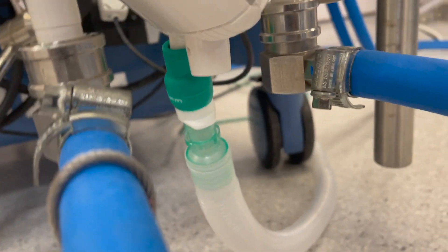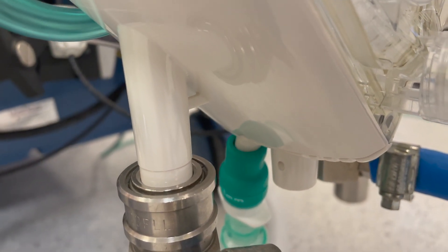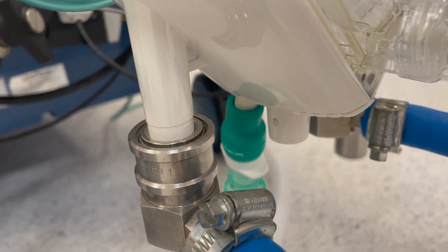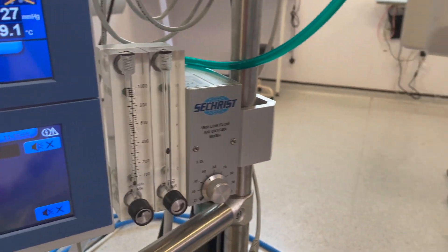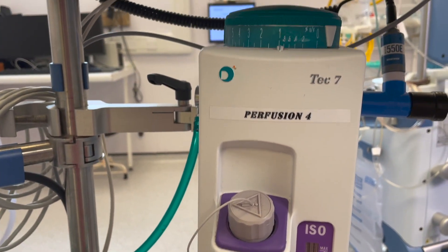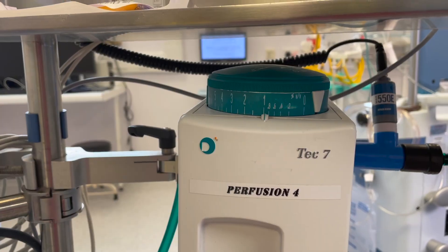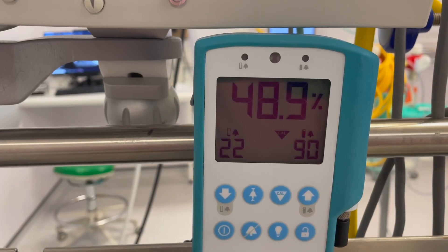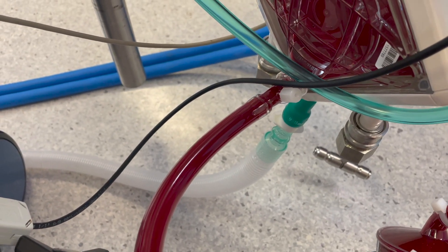Additionally, incorrect mounting on the back bar can result in the loss of sweep gas before it enters the oxygenator, resulting in poor oxygenation and inadequate depth of anesthesia. Reducing occupational exposure to volatile anesthetic agents is recommended during cardiopulmonary bypass. This is done with the scavenging system at the oxygenator gas outlet.